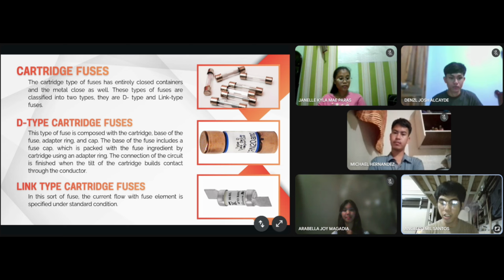For D-type cartridge fuses, it is called a D-type fuse because of its D-shaped body. It has four components: the cartridge, which contains the fuse element; the fuse cap, which holds the cartridge; and the adapter ring, which connects the fuse cap to the fuse base. When the fuse is fully screwed into its base, the tip of the cartridge makes contact with a conductor, completing the circuit. It is also known for high inrush current protection.